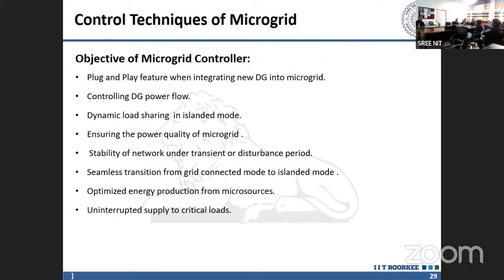Suppose your load is AC and the battery is DC — you use a converter to supply it. This is called droop, or power sharing: you have to decide through the controller. You may want a battery rated 0.7 to give its complete power, while the rest of the power comes from the other battery. So how to share power among different sources is something you must be able to control — as one source reaches its peak but load is still required, how much will the other sources supply? This is a very important issue in microgrids today: how the power sharing takes place.